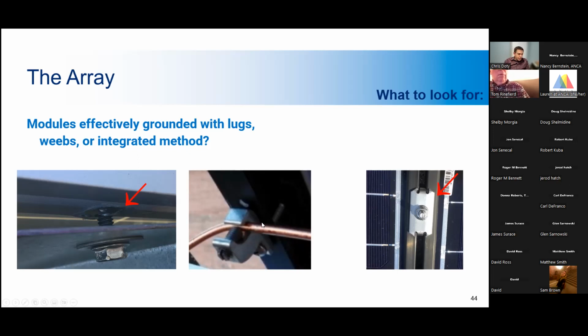And so this ground lug would be an example of non-integrated bonding, and this over here on the right is an example of integrated bonding. Basically, integrated bonding uses equipment that serves a dual function. So this mid clamp that you see in this picture is not only used to secure the modules in place, but it also is used to bond the modules to the racking. And like I said, many of the newer arrays use this type of bonding. And on the left, you can see here the screw is coming out, and in the middle, we have a ground lug with a ground wire run through, which is less common nowadays.